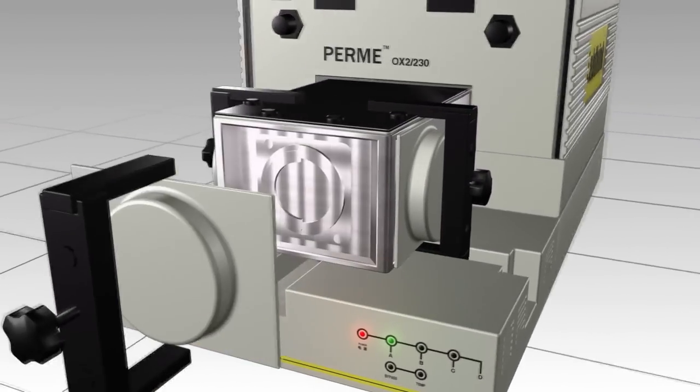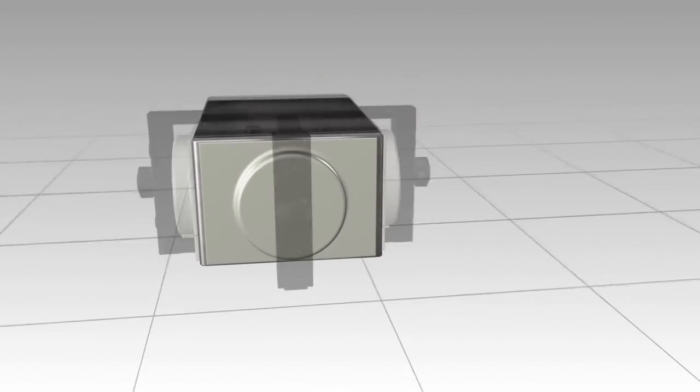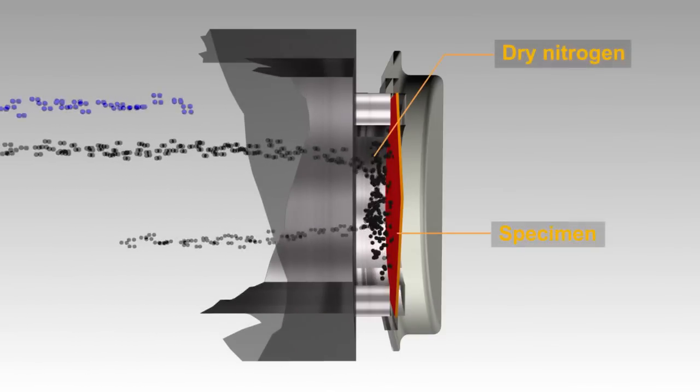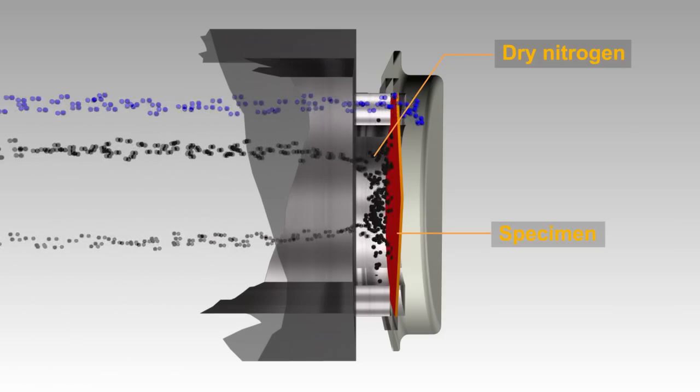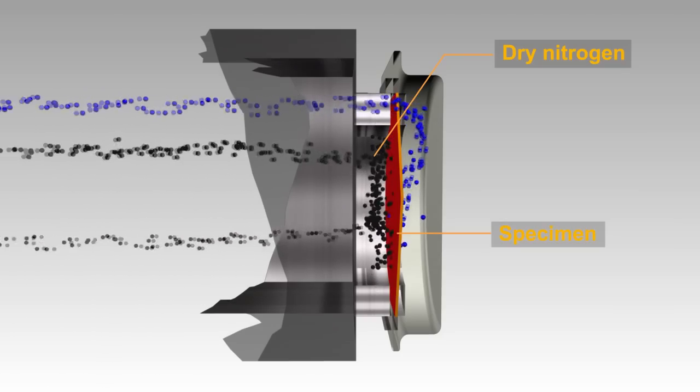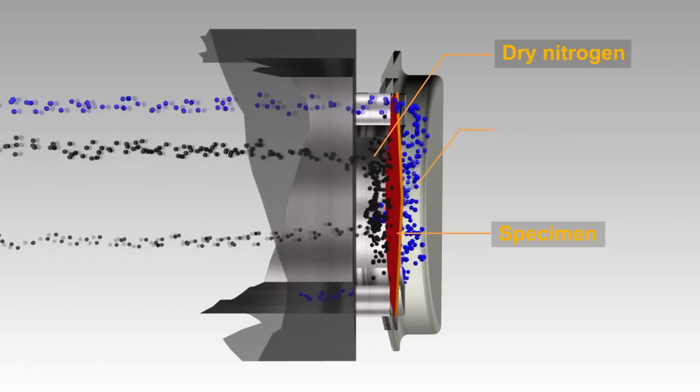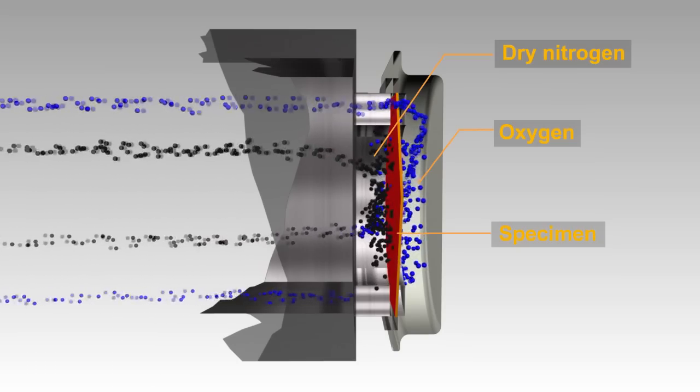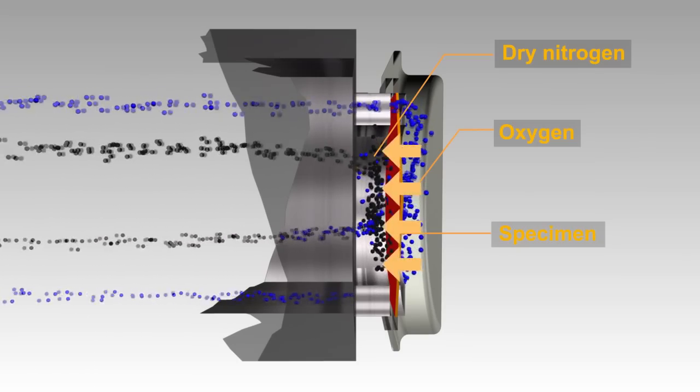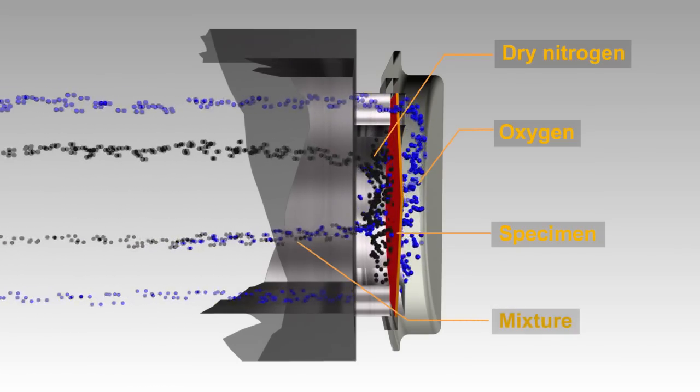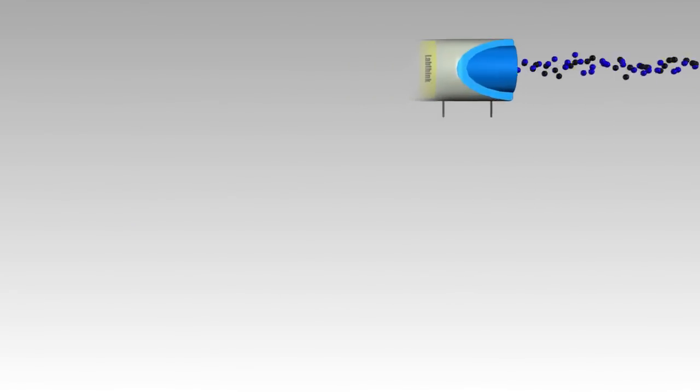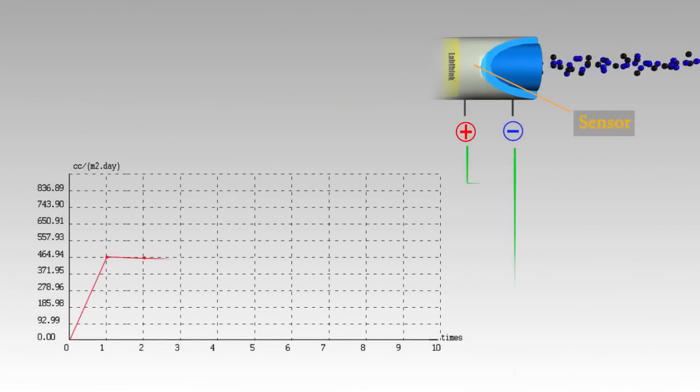OX2230 works by mounting the specimen between two test chambers at ambient atmospheric pressure. One chamber is slowly purged by a stream of nitrogen and the other chamber contains oxygen. As oxygen gas permeates through the film into the nitrogen carrier gas, it is then transported to the coulometric detector where it produces an electrical current.